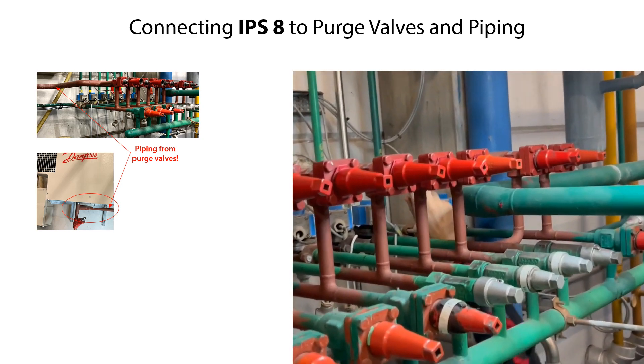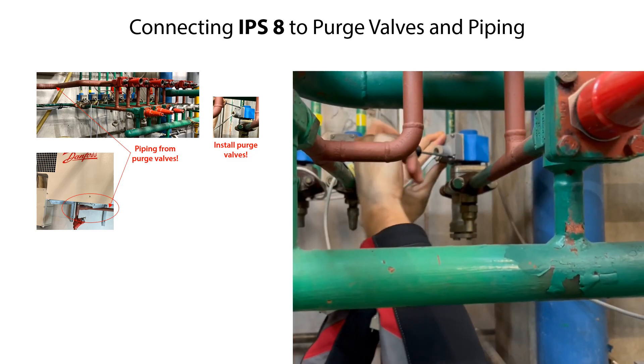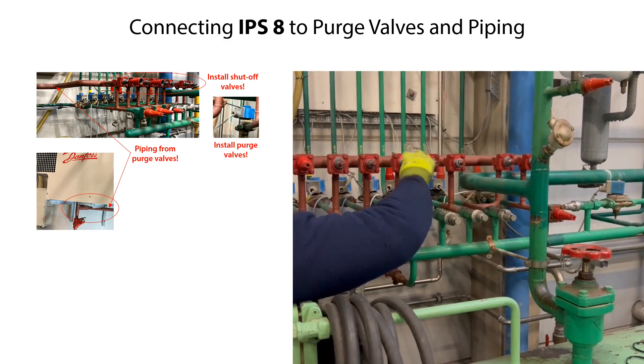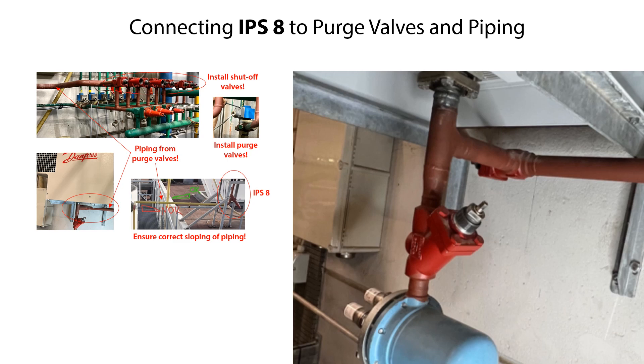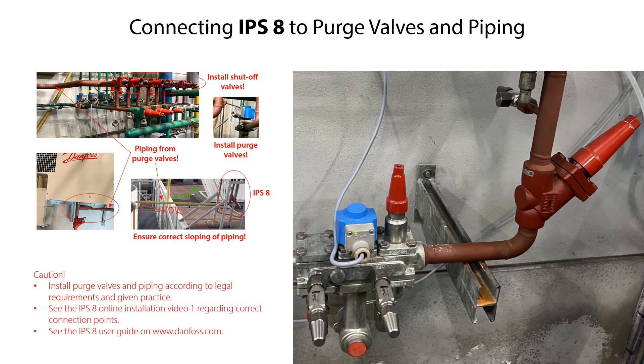Connect the IPS-8 weld flanges with piping to a suitable quantity and type of purge valves and suitable piping from the purge points, depending on the number of purge points needed. Here is an example of an installation with eight purge points. It is recommended to install shutoff valves between the IPS-8 and the purge valves. It is important to avoid liquid traps between the IPS-8 and the purge valves; therefore, ensure downward sloping piping flowing from the IPS-8. After installation of purge valves and piping, install other equipment and piping as needed, depending on the given application, according to legal requirements and given practice.